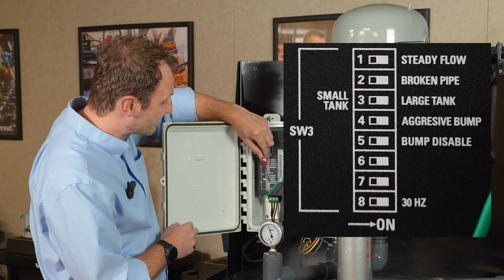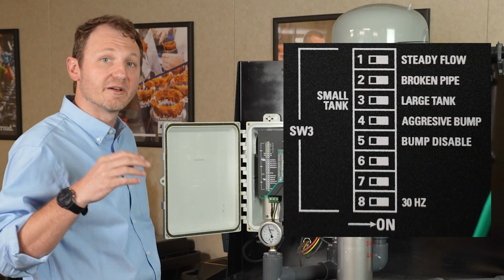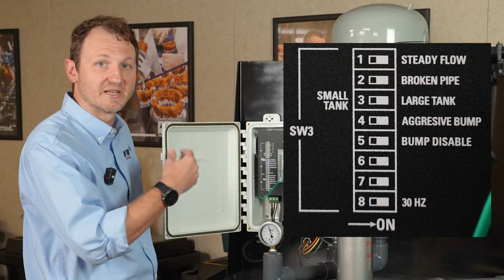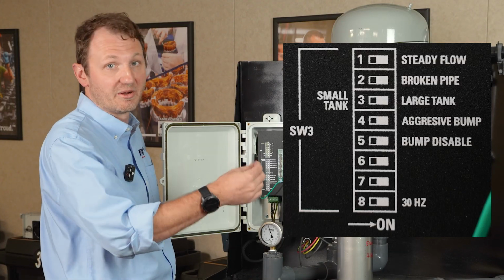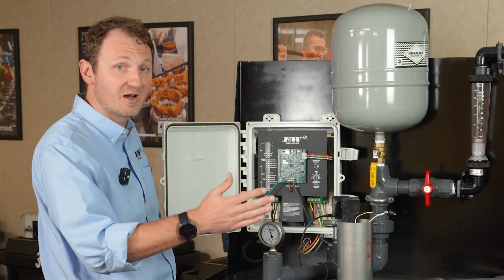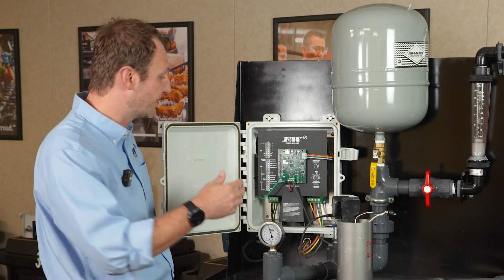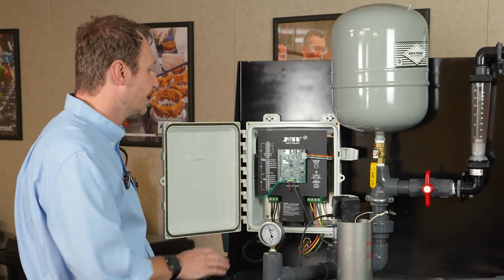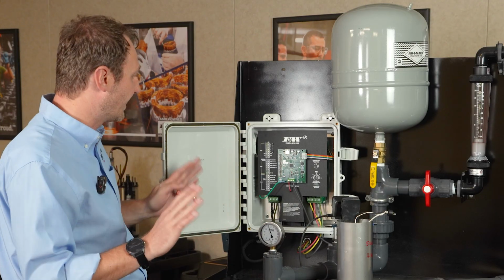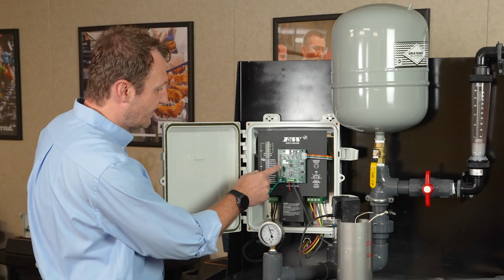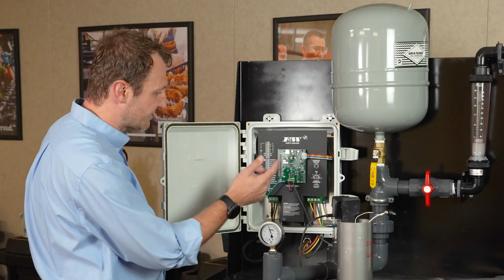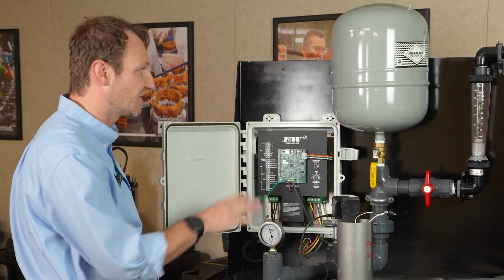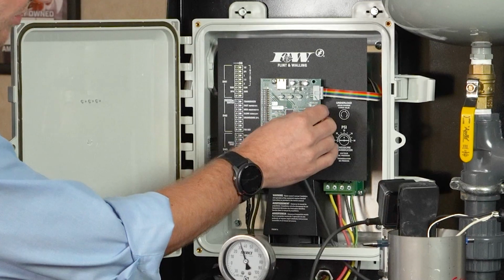And then the next 2 options, number 4 and number 5, are if we're operating with a pressure switch. So that's an aggressive bump or bump mode. So you can turn bump mode on or off, or you could add a little more aggressiveness to it by turning both of them on. Other than that, we're done. So we've got 1.5 horse, we've got it on 3-phase, we've got transducer, we've got broken pipe turned on, small tank. Want to confirm here a few things.